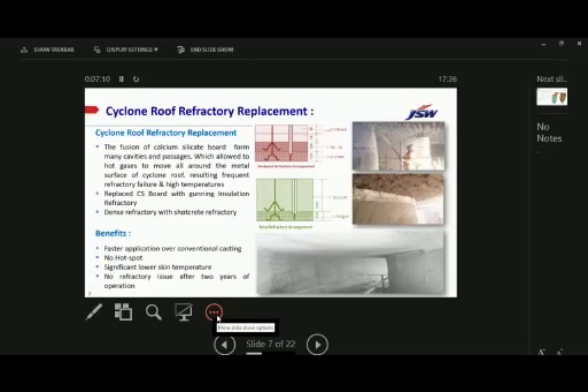whenever they come in contact, which leads to cutting of the anchors, and that leads to refractory failures. So to overcome these problems, the frequent failure of refractory, we adopted the gunning method over the conventional casting method.